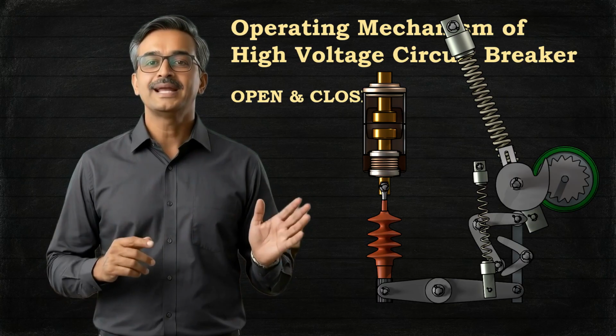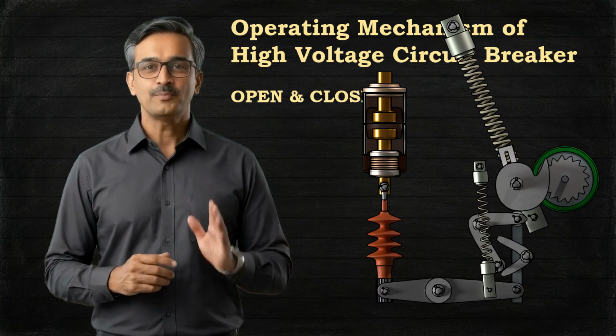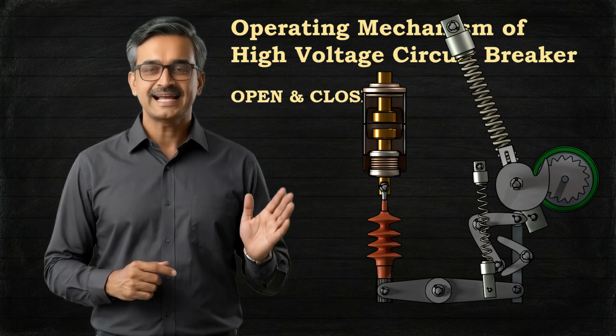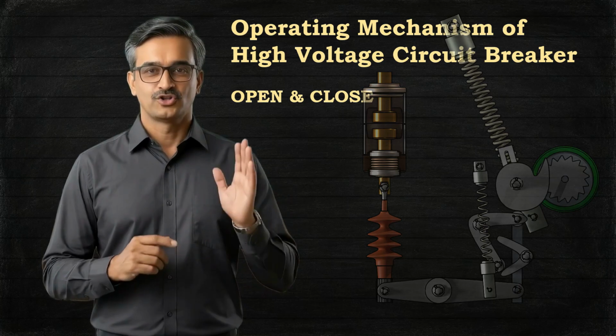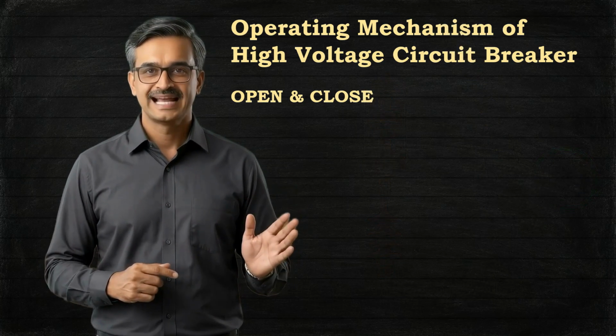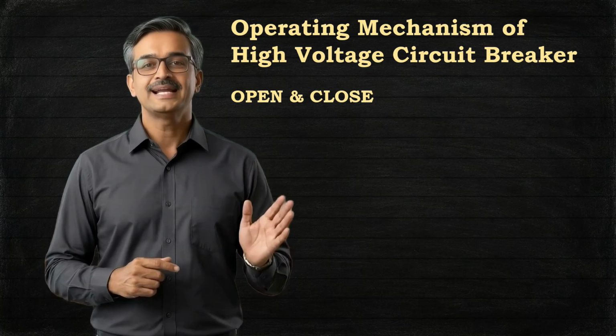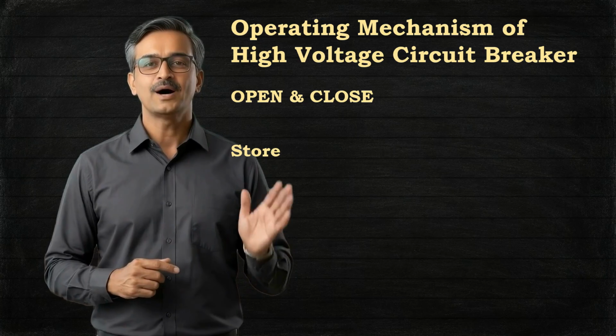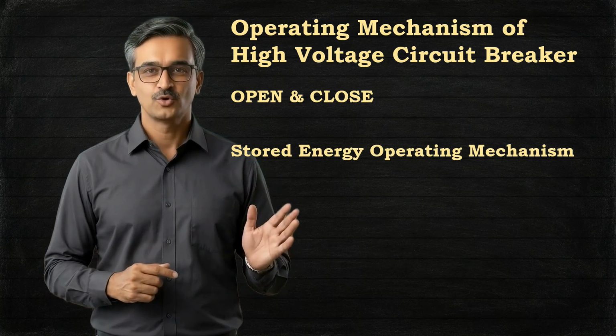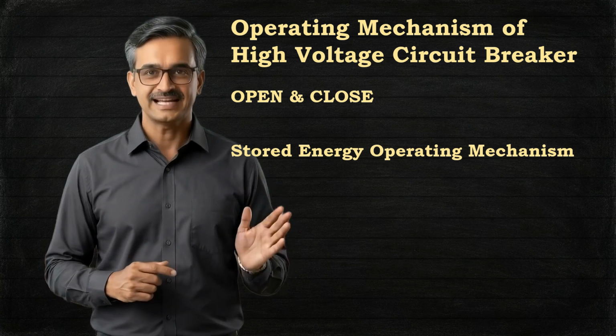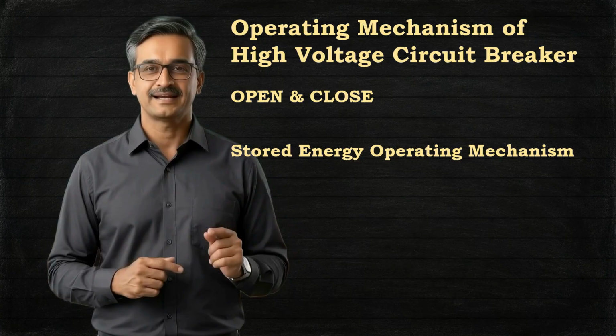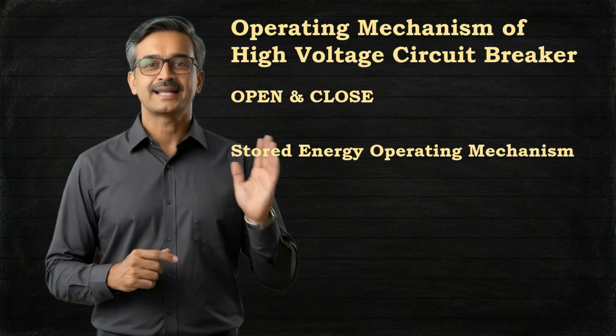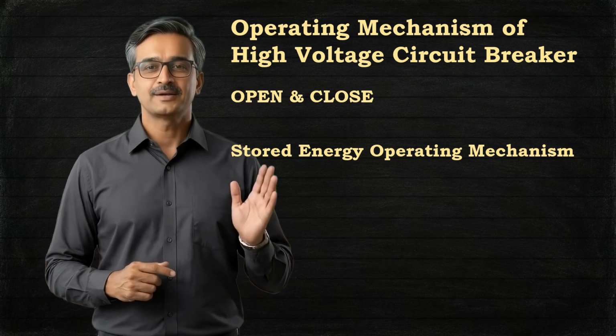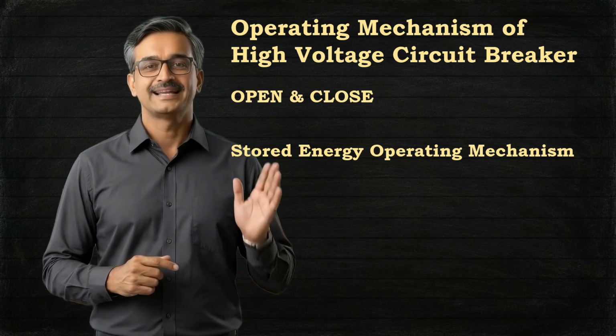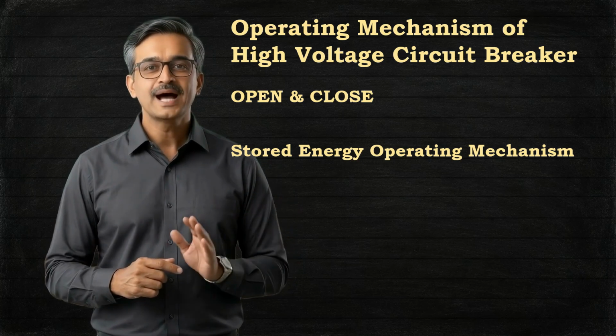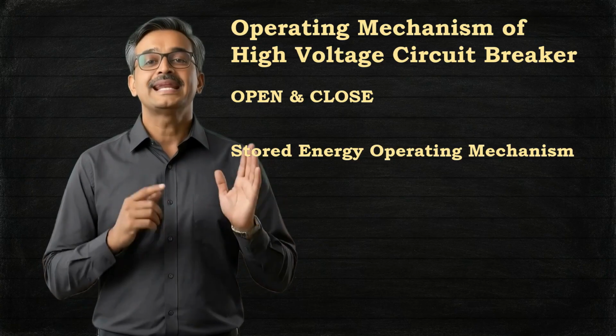The answer is the operating mechanism. Today, we shall understand how the operating mechanism stores energy and how it releases that energy whenever the circuit breaker receives a closing or tripping command. The operating mechanism used in modern extra high voltage or EHV circuit breakers is known as the stored energy operating mechanism. Now the obvious question is, why is it called a stored energy operating mechanism? Because the breaker stores mechanical energy before any operation is required. Then, whenever a closing or opening command is received, that stored energy is released immediately. This is why the breaker does not have to wait for an external power source at the exact moment of operation. Even if the control supply momentarily fluctuates, the required mechanical energy is already available.